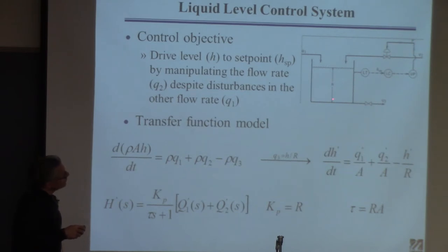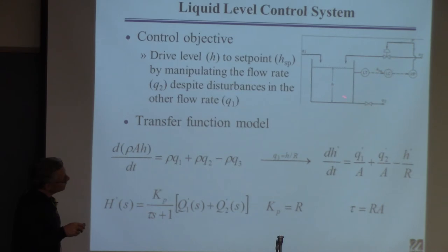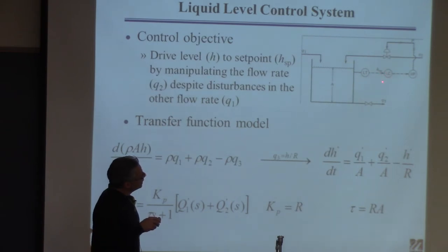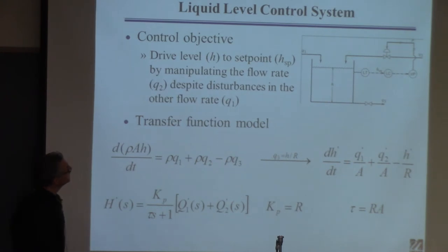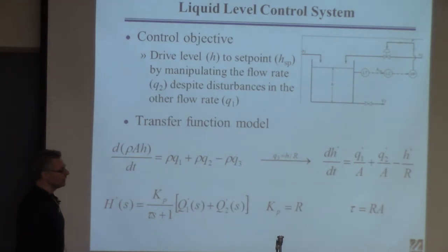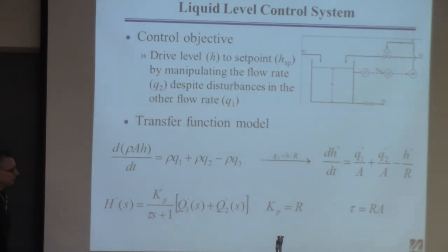Here is a motivating example: a liquid level system. We'd like to control the level in this tank. We have two streams coming in — we have no control over Q1, but we can control the flow of Q2. There is gravity-driven flow out. We measure the level, send that measurement to a controller which compares it to a set point, and the controller generates a signal to drive the valve through a current-to-pneumatic converter. So we manipulate Q2, and the primary disturbance is Q1.